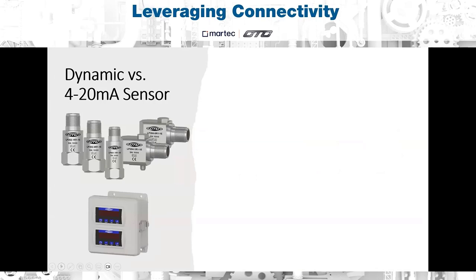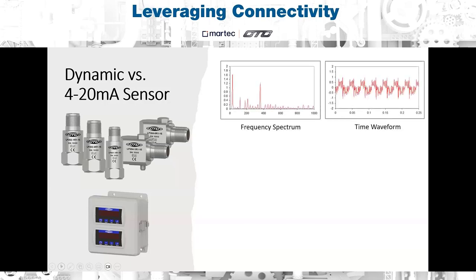So that was everything that I've covered so far are dynamic sensors. They fall under the dynamic sensor category. These sensors have an output that can be used for vibration analysis purposes. A trained vibration analyst can use the frequency spectrums and time waveform data to see issues in a machine like misalignment, bearing defects, imbalance, or lubrication issues. However, not all end users have this type of knowledge or capabilities.